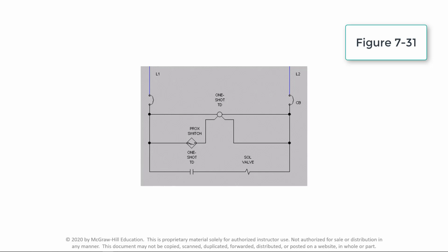The output contacts remain closed and TD continues to time for 10 seconds. Only when TD has timed out does its output contact open. After timeout, the one-shot is ready to be re-triggered for the next cycle.